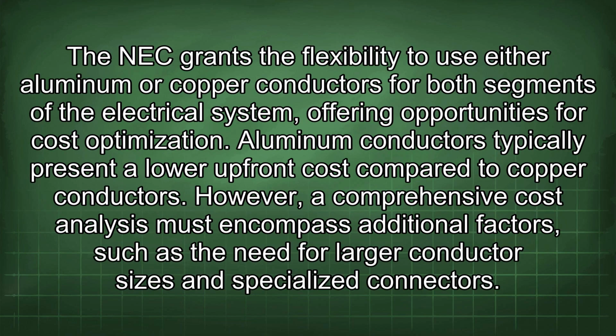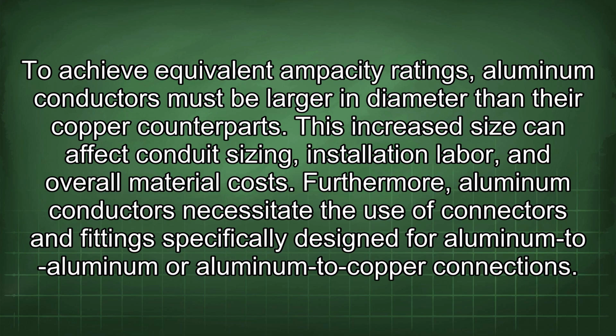The NEC grants the flexibility to use either aluminum or copper conductors for both segments of the electrical system, offering opportunities for cost optimization. Aluminum conductors typically present a lower upfront cost compared to copper conductors. However, a comprehensive cost analysis must encompass additional factors, such as the need for larger conductor sizes and specialized connectors. To achieve equivalent ampacity ratings, aluminum conductors must be larger in diameter than their copper counterparts. This increased size can affect conduit sizing, installation labor, and overall material costs.